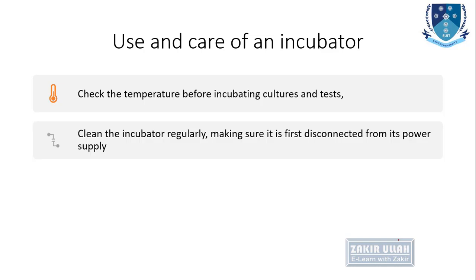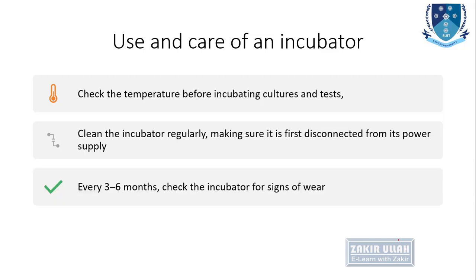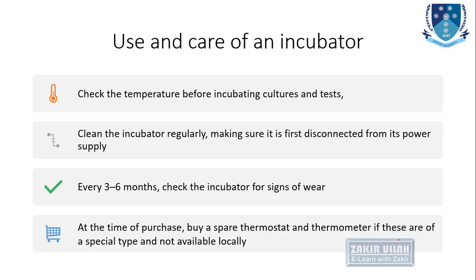Also clean the incubator regularly, and make sure that before cleaning it is disconnected from the power supply. Check for any signs of wear, cuts or cracks every 3 to 6 months, and then maintain or repair any such signs.